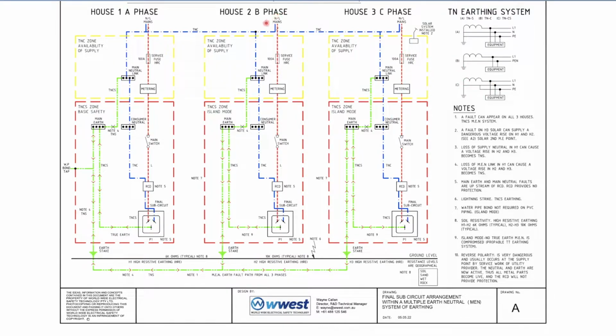So when we come back over here to house 1, you've got your active and neutral coming in. Typically it's two separate cables that come in, an active and a neutral. As it says in this zone, it's a TNC, because your neutral and your earth are combined as they come into your switchboard. The active comes in and goes down through your service fuse, through your metering, through your main switch, all the way to your RCD, then to your final subcircuit, out to your power point. And it's at the power point that it reaches the TNCS.